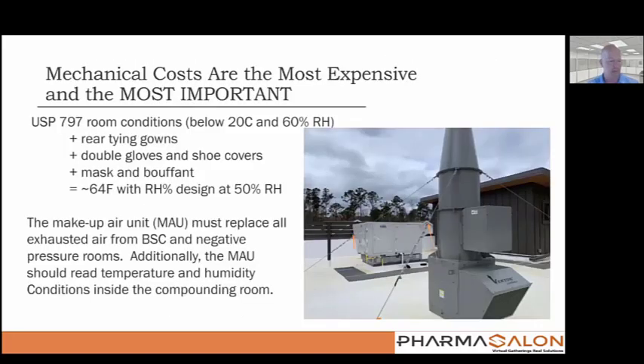So where's the majority of your money going? Well, if you look at both Table 2 and Table 3 in chapter USP 800, you'll see that both of them called it the CSEC, that is the Containment Secondary Engineering Control. That's a fancy name for our compounding room, which is under negative pressure. Both of those, sterile and non-sterile CSECs, must be externally vented.